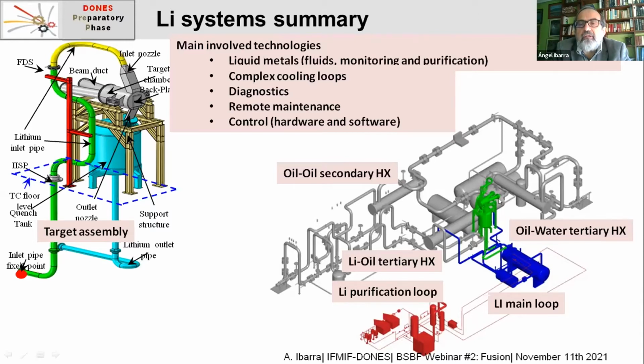In this figure, you can see in green... Okay, the lithium does not like water too much, and to reduce the risk of interaction of lithium with water, we have two oil intermediate loops, in such a way that we have a heat exchanger lithium to oil. Then we have another heat exchanger, oil, and the third one is between oil and water. With this complex configuration of intermediate loops, we are able to extract the heat from the lithium to the water, reducing the risk of contamination and interaction of lithium with water.